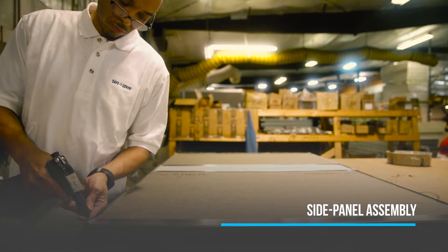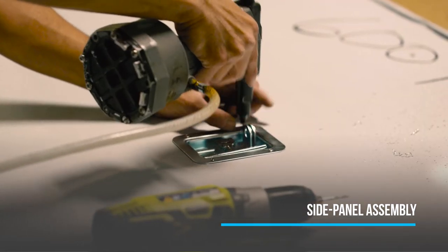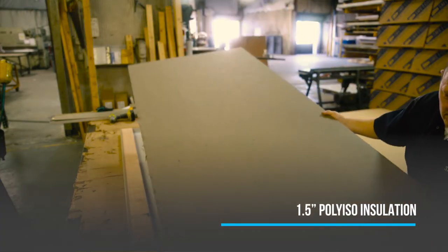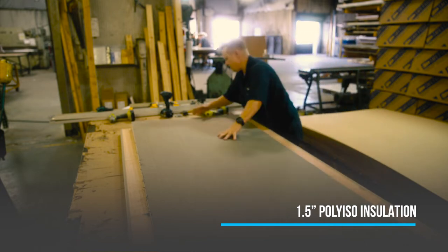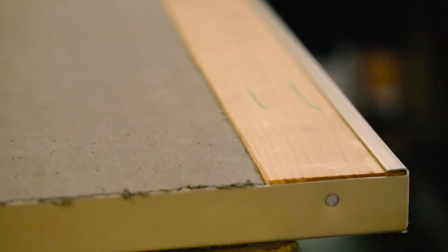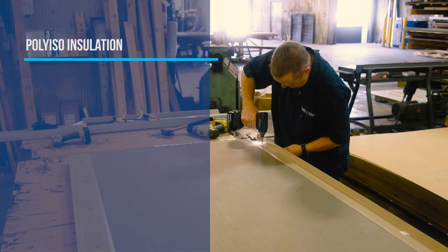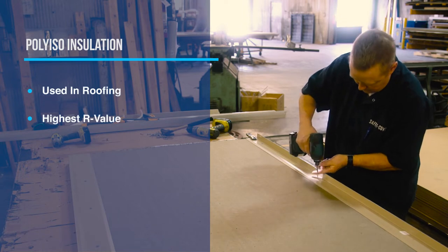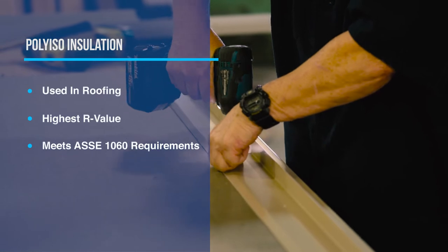The first step in the construction of an outdoor above-ground enclosure is the side panel assembly. Each side panel is fitted with 1.5 inches of poly-ISO insulation that is cut to the exact dimensions of the panel. This is standard for most Safe-T-Cover enclosures. This type of insulation is commonly used in roofing, has the highest R-value for rigid board insulation, and ensures our enclosures meet ASSE 1060 requirements.